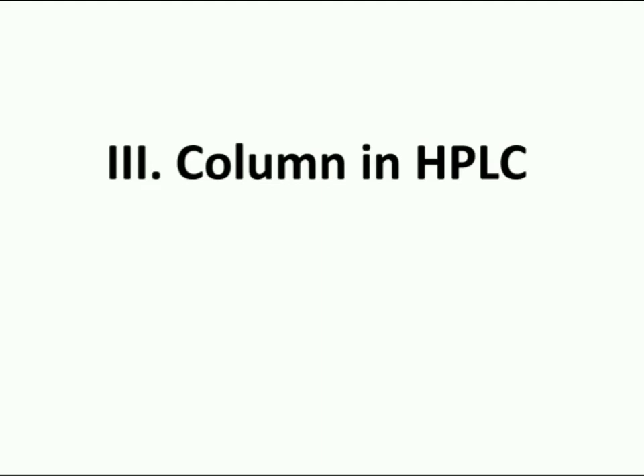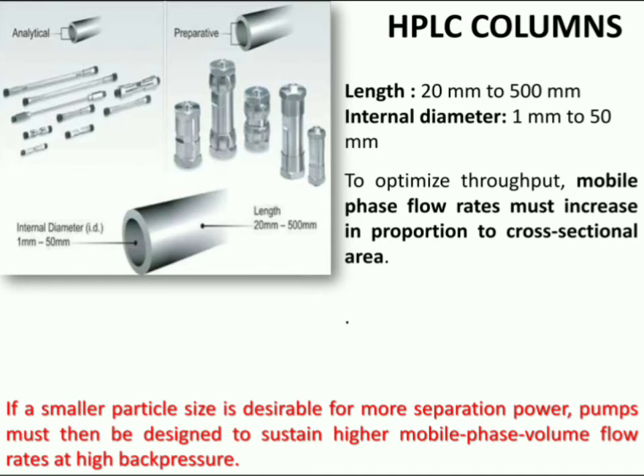The third and most important part of the HPLC system is the column, where the separation is performed. Recent columns are often prepared of stainless steel material instead of glass, because stainless steel is tolerant towards a large variety of solvents. The packing material generally used is silica or polymer gels, compared to calcium carbonate.